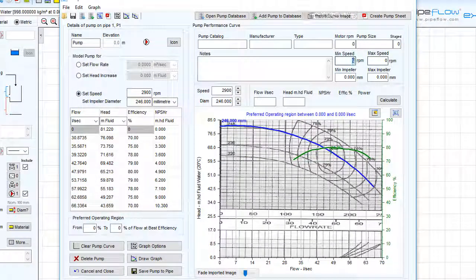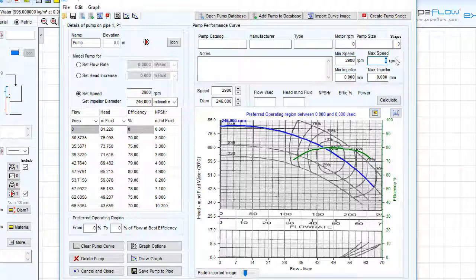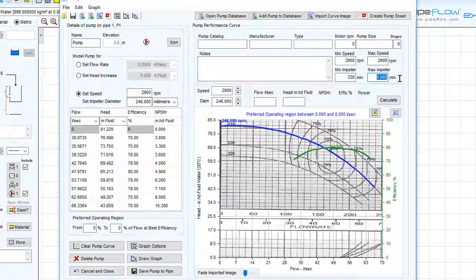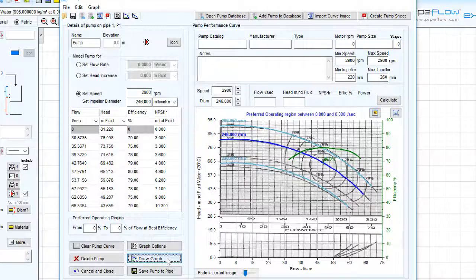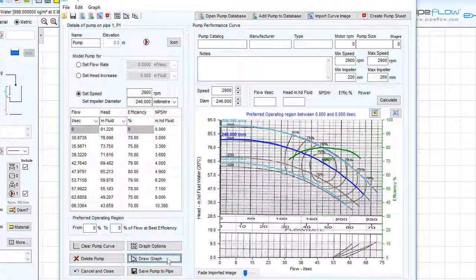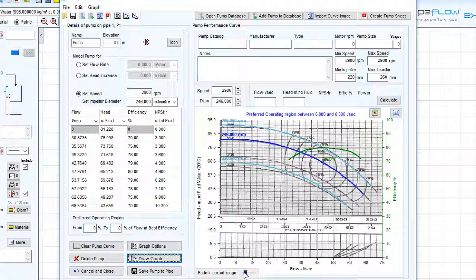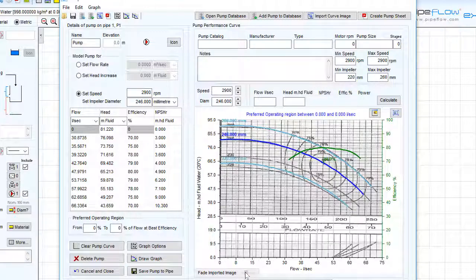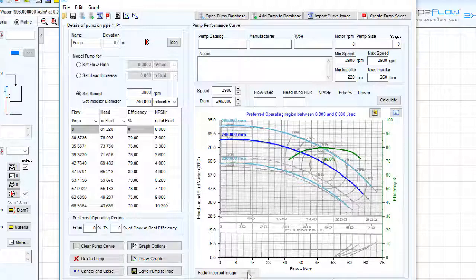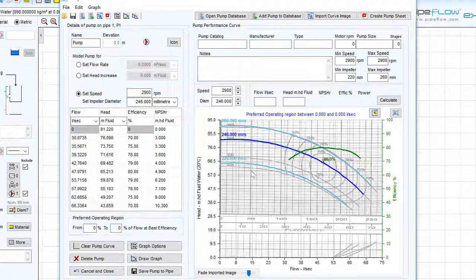Entering the specified minimum and maximum speed and impeller diameters will allow the Pipeflow Expert software to draw an envelope. Clicking the draw graph button and using the slider to fade the background image, we can see that the minimum impeller diameter curve doesn't quite match up with Pipeflow Expert's prediction.